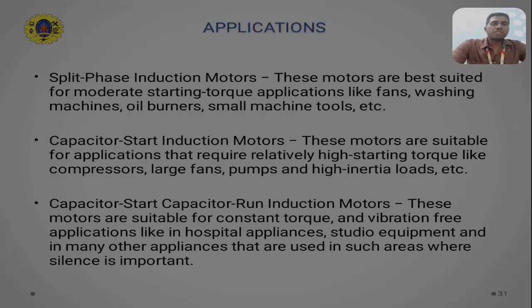The advantage of this third type is that it not only creates a high initial torque but also ensures smooth operation, since the capacitor C1, a low value capacitor in series with the starting winding, will always be connected in the circuit. So this capacitor C1 will ensure the smooth operation of the single phase induction motor, right?